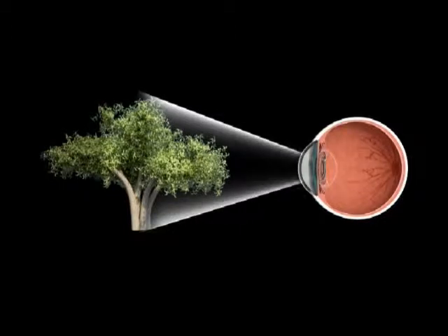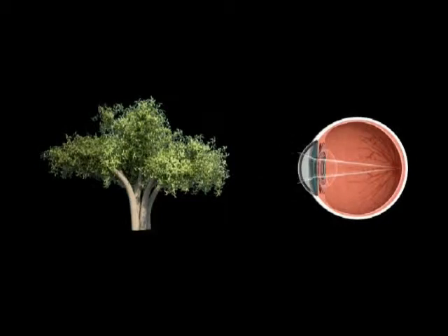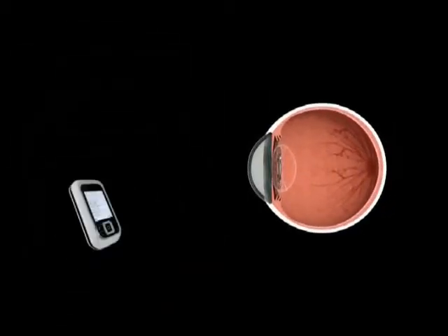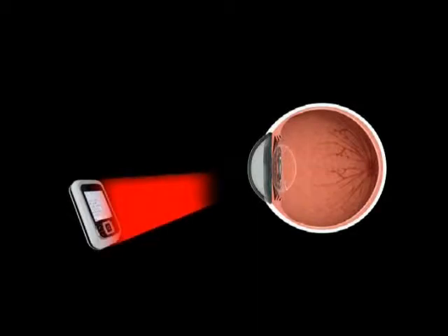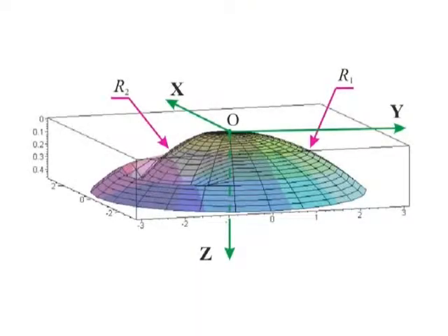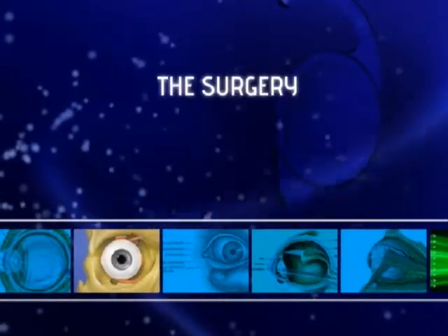No ghost or double images should be propagated, and significantly less glare and halo effects should appear. These images for far and for near are clearly separated and will be exactly in line with each other, without image jump on the concentric optical zones produced by either refractive or diffractive rotational symmetrical intraocular lenses. Overlapping is thus reduced, and neuroadaptation will play a minor role in the performance of the lens.